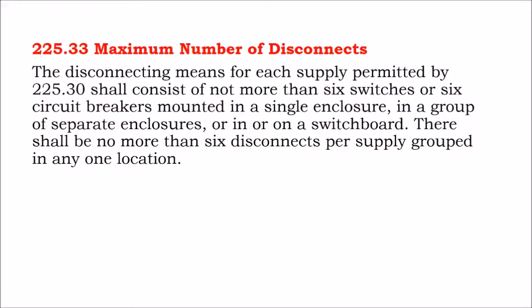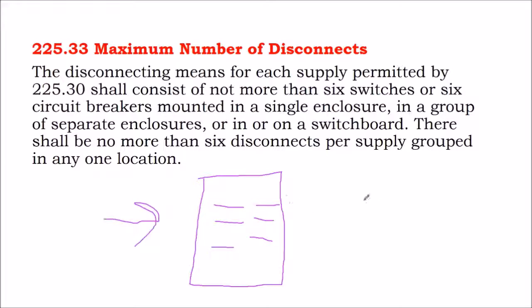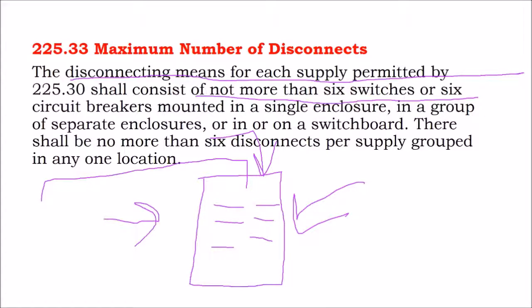Finally, we get to another disconnect rule, the maximum number of disconnects. This is known as the 6-handle rule. And it says the disconnecting means for each supply permitted by 225.30 shall consist of not more than 6 switches or 6 circuit breakers mounted in a single enclosure. Well, what does that mean? Well, we know what an enclosure of switches is. It's our electric service panel. And so what it says is, here's an electric service panel, and it has 6 switches on it, and it's being fed by a supply, and let's say that's our supply coming in from the top. The disconnecting means for each supply shall consist of not more than 6 switches.